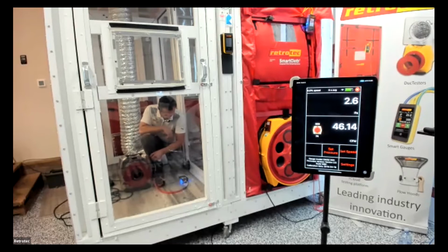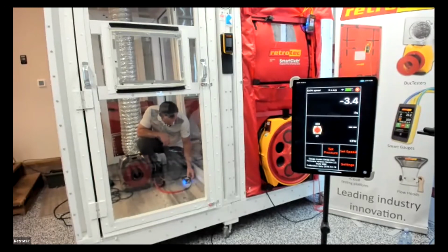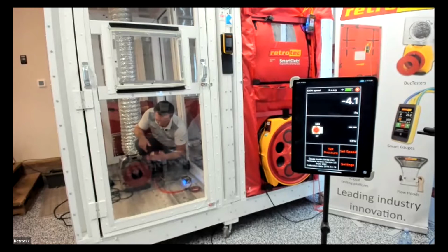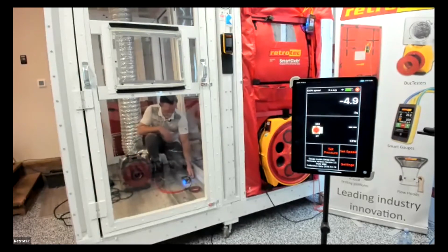That's why it's important to have the right setting selected, or you'll get some wonky numbers. Yeah, so even when we still got the 0 there, it was too open. So on the gauge, I'm going to change. The next one down is 47. And we're also on the 300 selection instead of 340, which isn't going to make too big of a difference. But we do know that we need to go down. So 74 to 47. We've got the 340 now selected. We've got the 47 range selected. And we'll try this again.